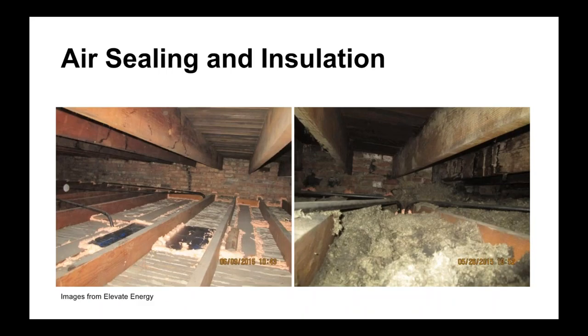So how do you address those leaks? By air sealing and insulation. Air leakage is caused by a hole between zones — between the inside and the outside — and a pressure to push air through that hole. Those holes can be windows, doors, seams between wall and floor, recessed lights, or intermediate zones like attics, basements, and crawl spaces. The pressure occurs from stack effect, a byproduct of convection inside the building. Hot air rises because it's less dense, causing cooler outdoor air to infiltrate from the bottom to replace it — so there's air being drawn in at the bottom and hotter air pushed up at the top during winter.